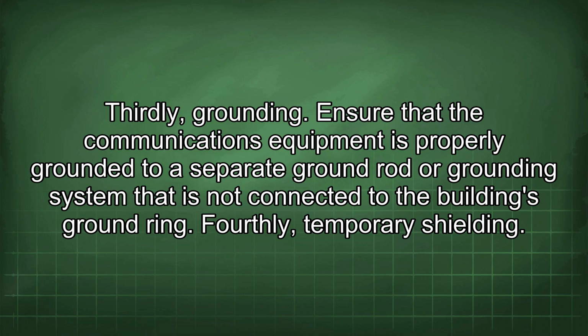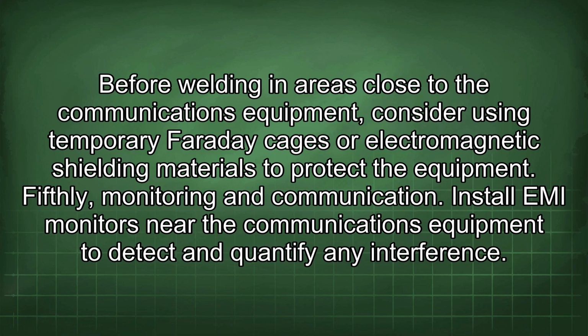Thirdly, grounding. Ensure that the communications equipment is properly grounded to a separate ground rod or grounding system that is not connected to the building's ground ring. Fourthly, temporary shielding. Before welding in areas close to the communications equipment, consider using temporary Faraday cages or electromagnetic shielding materials to protect the equipment.